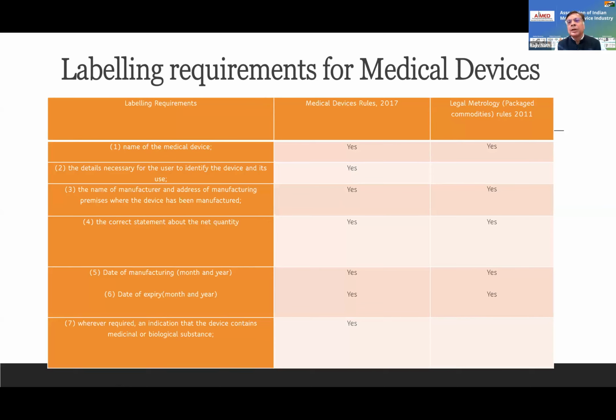What is unit pack of sale? It can be a single piece. It can be a package of 10 pieces. It is the pack at which not less than that pack size will be sold to a consumer. That becomes the unit of sale. So if you buy insulin syringes which have 10 syringes packed inside, the unit of sale is not one single syringe, it is a pack of 10 syringes. So on that unit of sale, these are the labeling requirements.